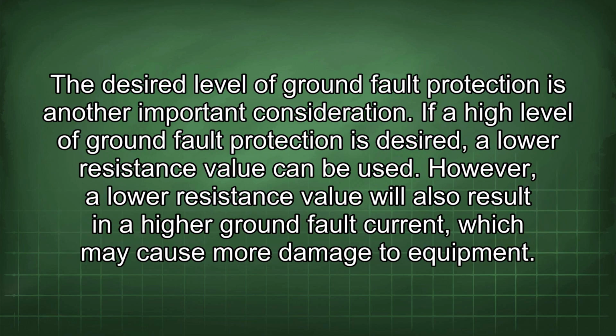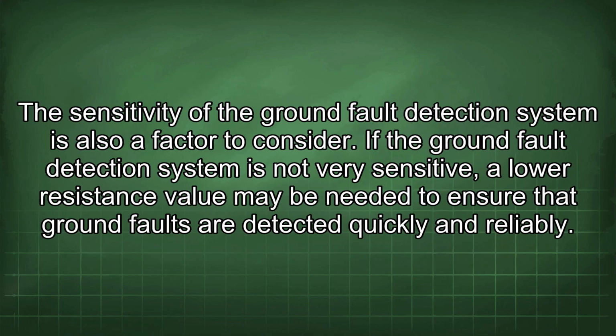The desired level of ground fault protection is another important consideration. If a high level of ground fault protection is desired, a low resistance value can be used. However, a lower resistance value will also result in a higher ground fault current, which may cause more damage to equipment. The sensitivity of the ground fault detection system is also a factor to consider. If the ground fault detection system is not very sensitive, a lower resistance value may be needed to ensure that ground faults are detected quickly and reliably.